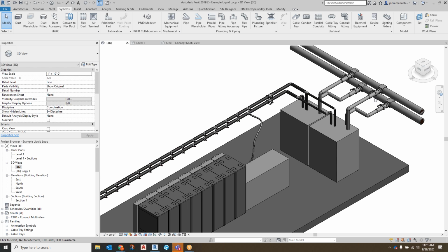Initially I was thinking about 250s being a standard reference design size, which is probably fairly much a standard, but by the time we finish this percolation, we'll find more and more people selling data center units of 500 kW of liquid. So if we arbitrarily try a pilot project right now, say for 500 kW, came up with a specified velocity, a specified delta T, and see how much we can work around that, and see if it's a useful model for future discussions, for sizing, for other things, not just the pipe but potentially the footprint of the CDU, the footprint of the heat exchanger, and the downstream distribution pipe. And recognizing all these will be based on a fictitious set of numbers that are reasonable but not necessarily what we're going to see.